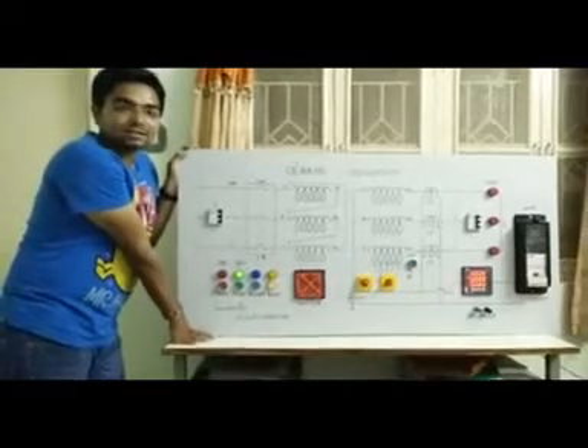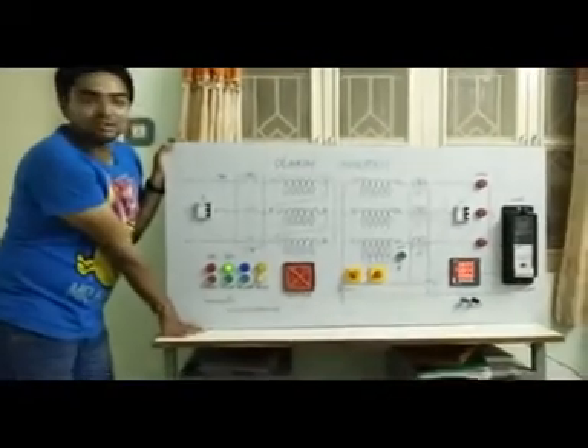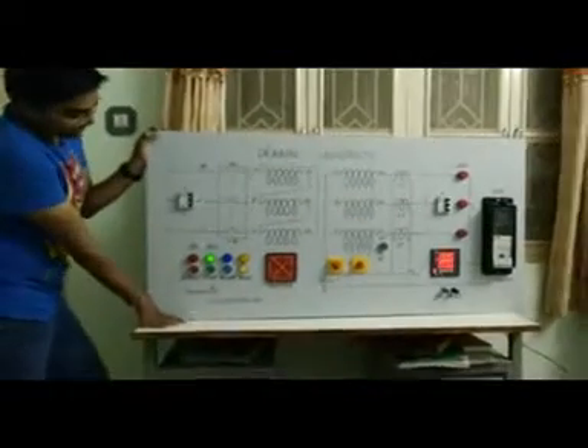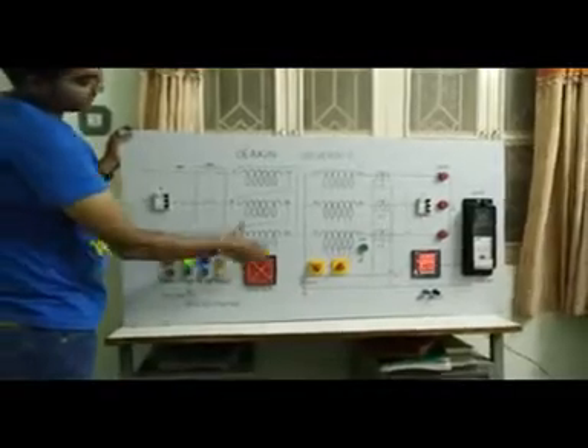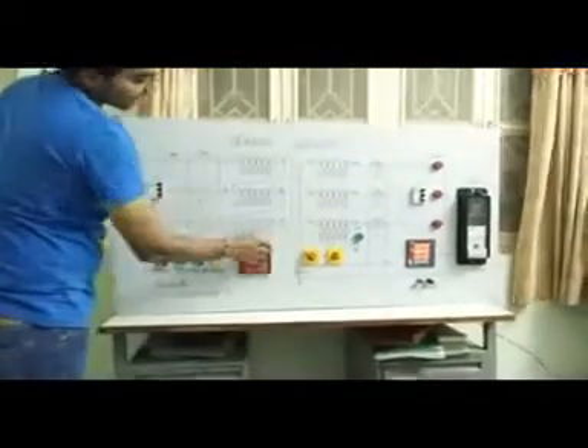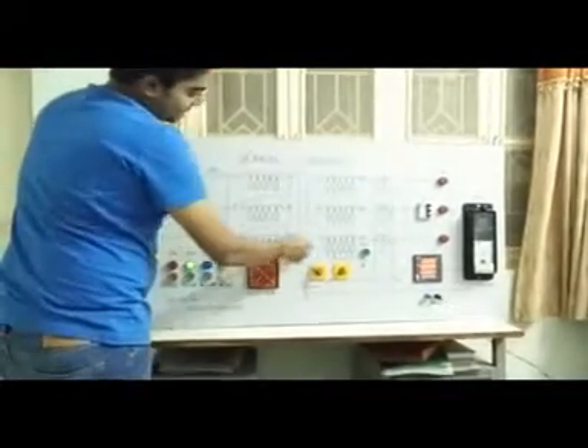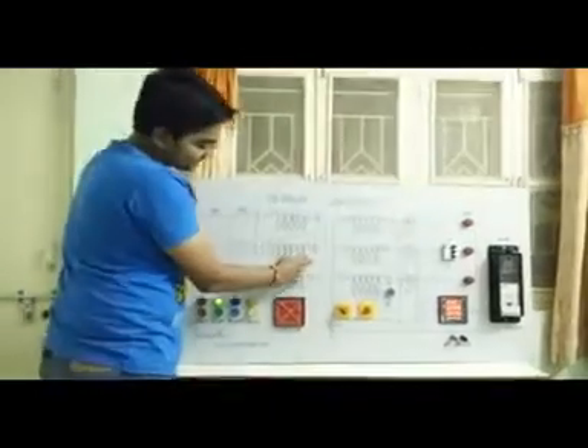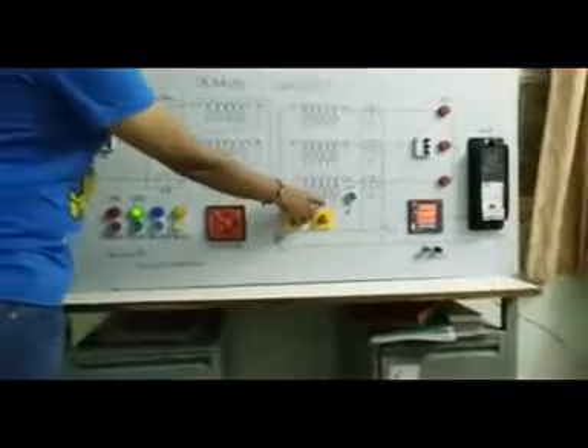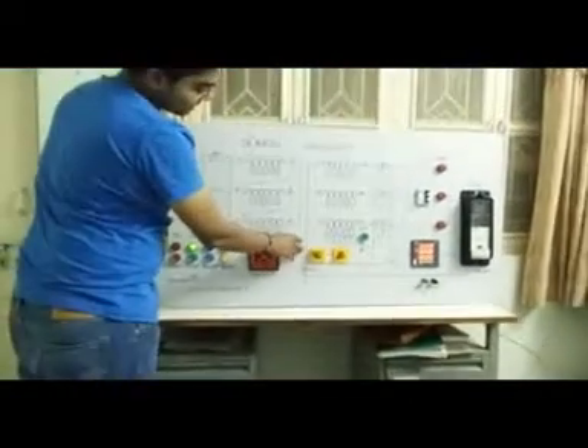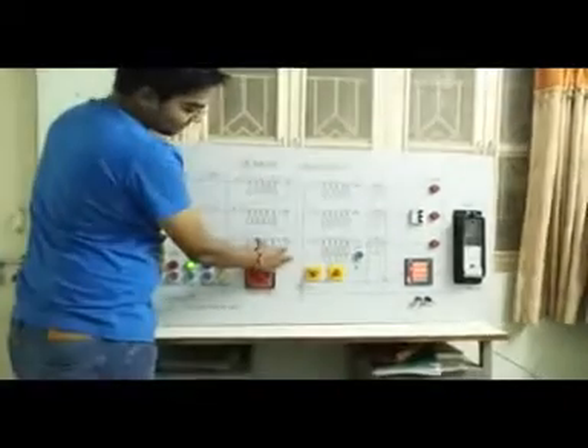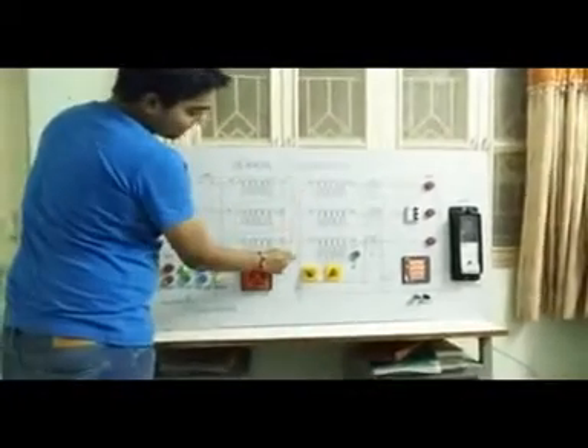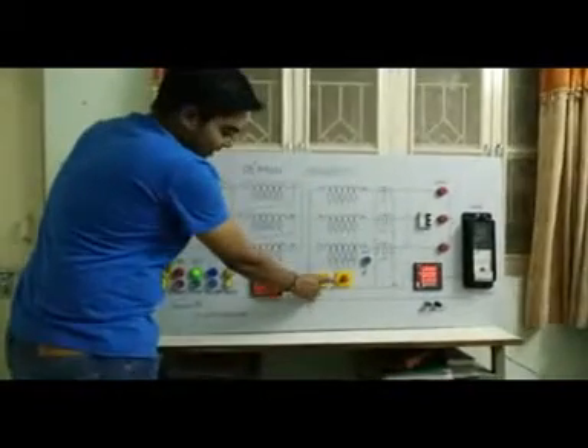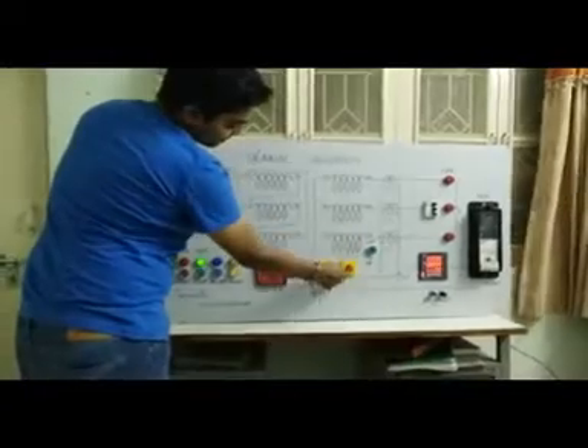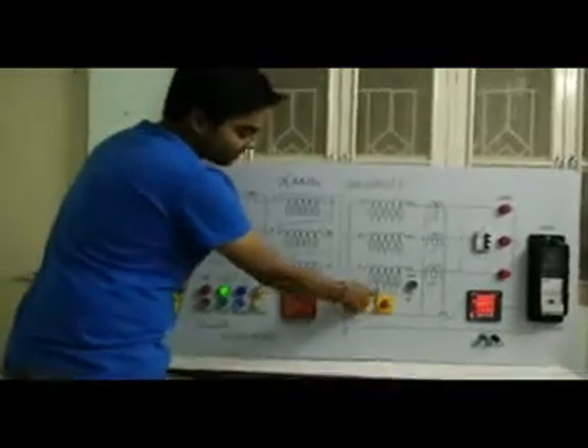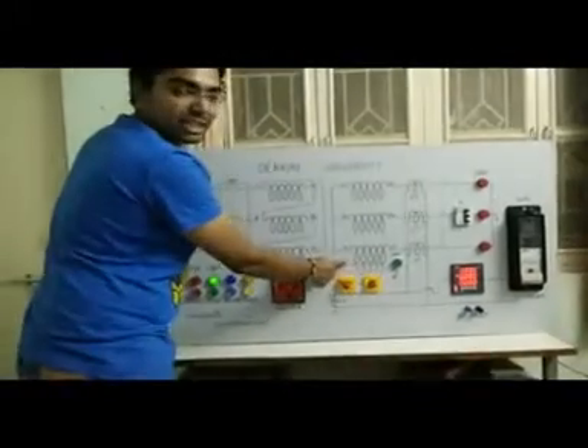The points that I covered in the last simulation, I will show all of them in this hardware simulation of the project. This is the circuit breaker. This is the real transformer, the primary and the secondary. In the secondary of the transformer, we have made the tappings, which are 5%, 10%, 20, 30, and 100%. To select the phase of the transformer, we have placed the phase selector switch, and to select the tapping, we have placed the tapping selector switch. So with this, we can select the tapping on the secondary of the transformer.